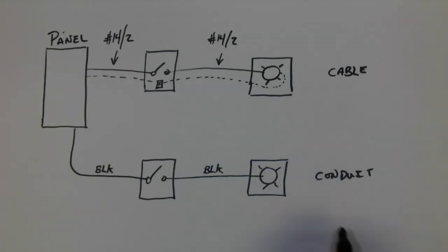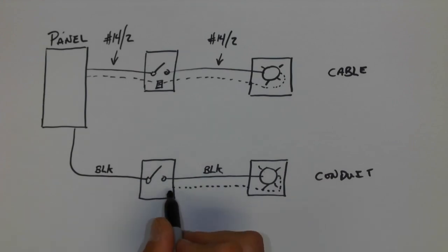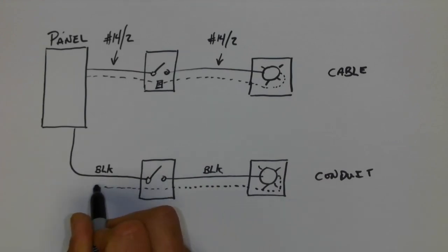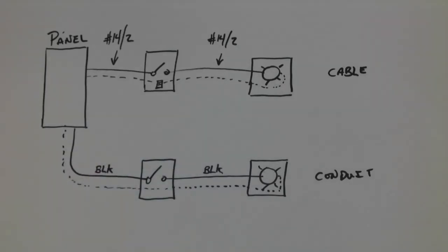And then traveling all the way back would be a white conductor. And there would be no marette anywhere within the circuit because it has no connection to the light switch. So this was a common way for us to do our circuits, and this is the way that is now required under the Canadian Electrical Code from 2018 going onward.